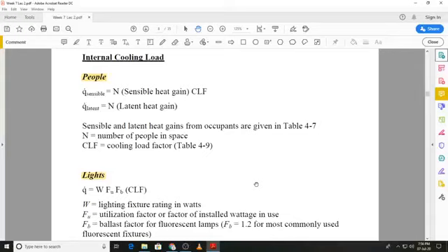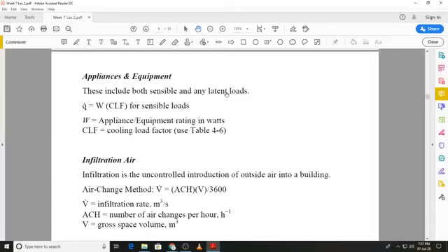You would have seen that if we look at the old tube lights that we have, there is what we call a choke or a ballast just behind the tube light, and that is also emitting or causing thermal load in the conditioned space. So that is what we mean by the ballast factor, and for light fixtures this value is provided by the manufacturers. For appliances and equipment, if the appliance is only generating a sensible load, then we multiply the wattage by the cooling load factor, and if it has a sensible and latent load, then we add that latent load to the sensible load, and the cooling load factor again will be obtained from a table.